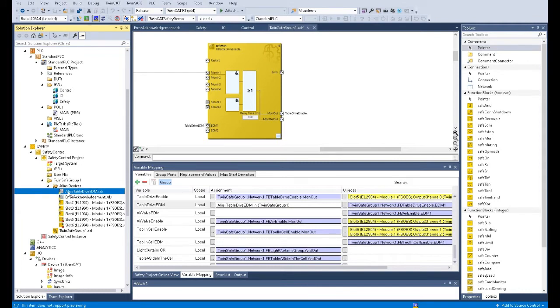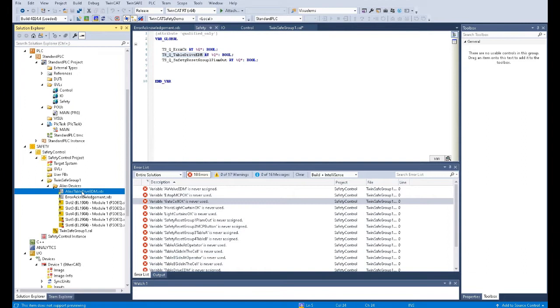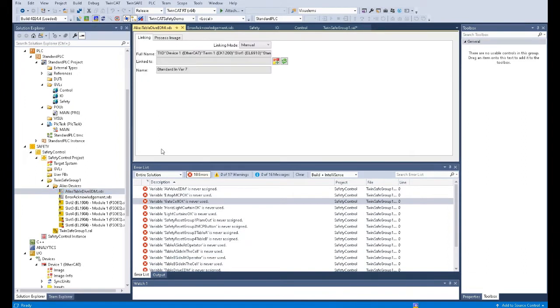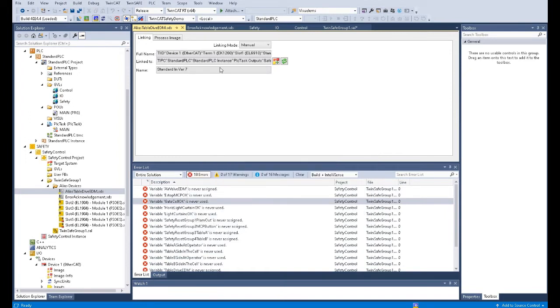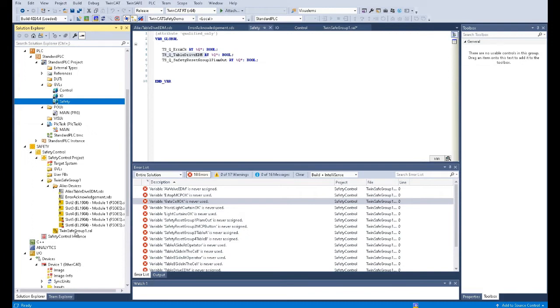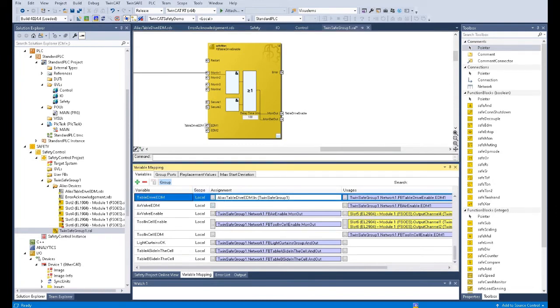We click 'in' and click OK, which means we connect this safety tag with this alias tag. After that, we need to connect this alias tag to our standard PLC tag. Double-click the alias 'table drive EDM,' click, and select 'TS_Q_table drive EDM.' Using this approach, this tag serves as a bridge connecting the tag from the standard PLC through the variable mapping to the safety area. The actual safety tag connects to this alias tag.